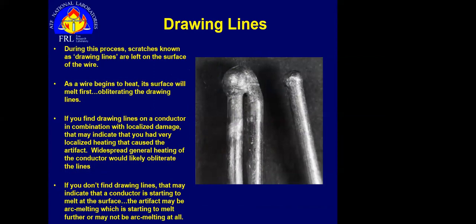If you still see these on your conductors, they are probably one of the best indicators that your conductor wasn't on the verge of melting by fire impingement, because fire is going to be melting the entire mass of that conductor. And because these are so minute, they should be one of the first characteristics that are obliterated by fire impingement.